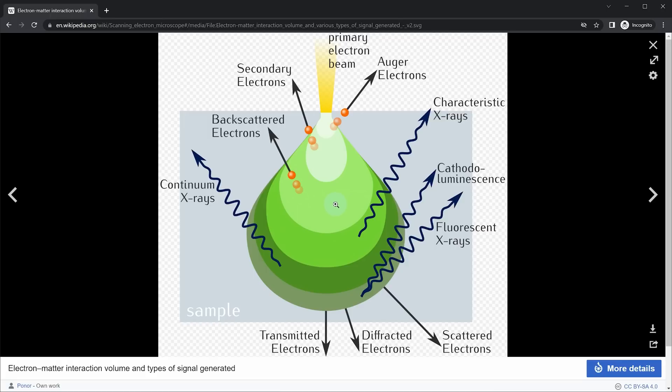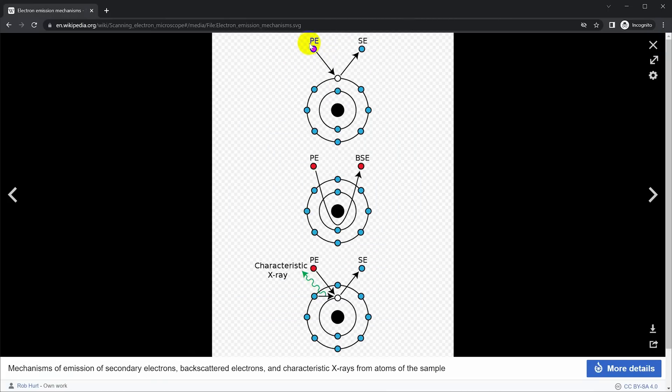And that can allow the scanning electron microscope to both produce an image but also to identify some of the properties of the sample. For example, a primary electron can come in and just knock an electron back out and so you get a secondary electron. You can get back scattered electrons where a primary electron comes in and just gets rejected back out. And you can also have a situation where a primary electron knocks a secondary electron out, but then an electron from a higher orbital will drop in and then emit some energy as x-rays. And that again helps you to identify materials in the sample.